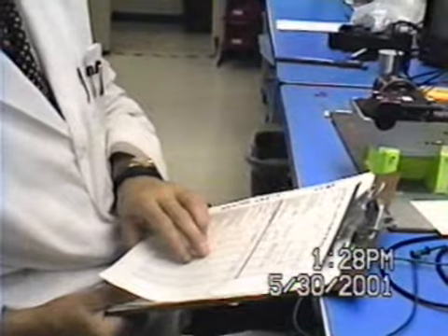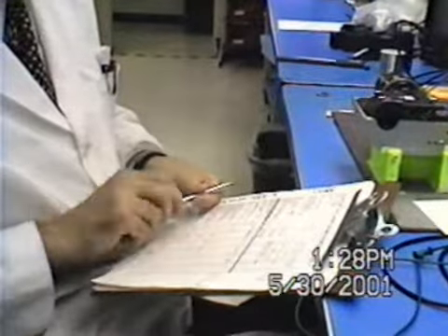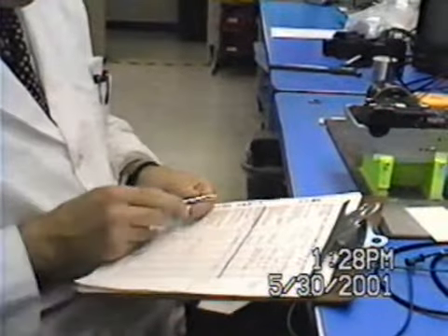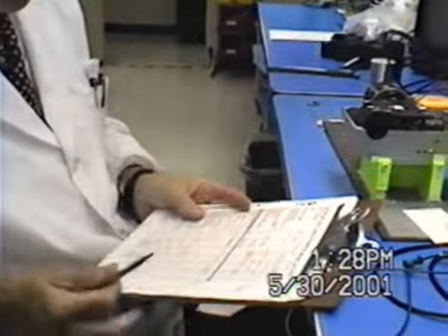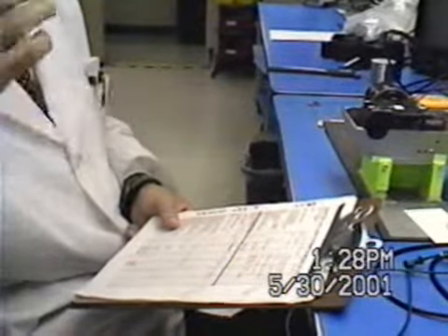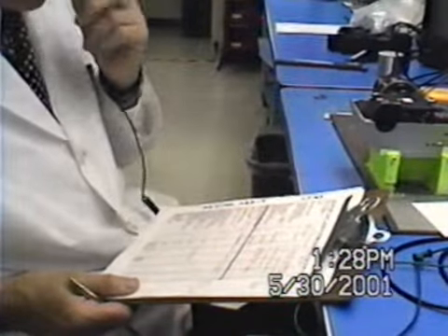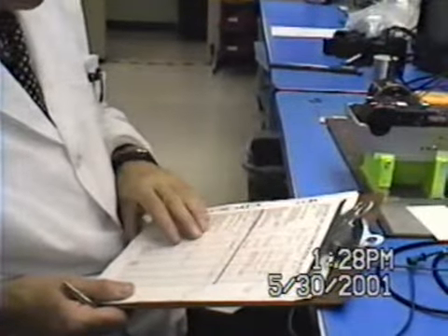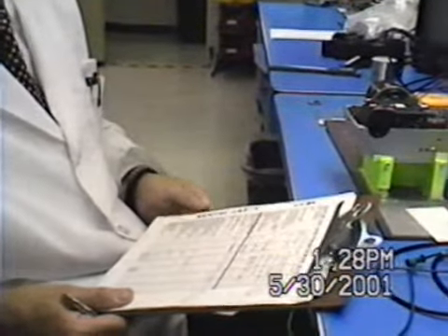that the R109 resistor had to be changed from its old 36 kilo ohm value to something like 18 or so. Well, we put in a little more, 30K, so as to stay within the adjustment range. So we put in 30 kilo ohm, and now the emissivity reading was something like 34, 30 something. No, I'm sorry, it was 19, I think, 19 or 20. 16? Okay, it was 16.